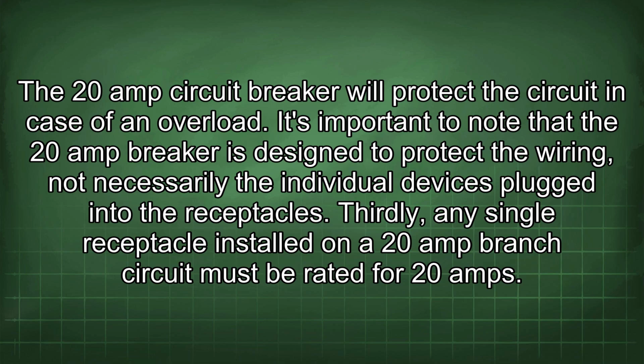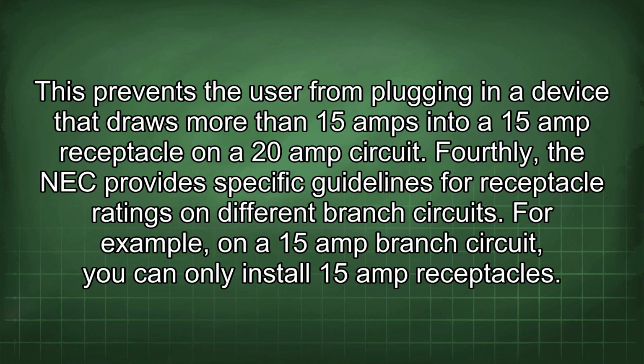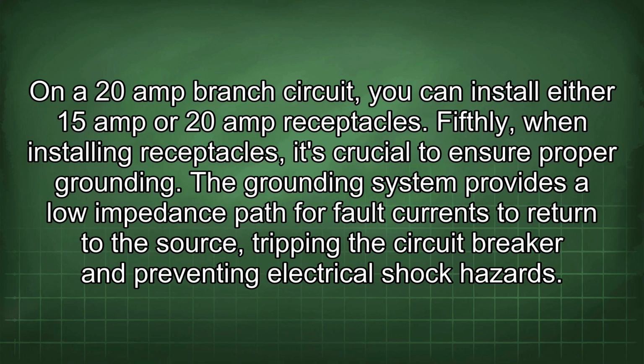plugged into the receptacles. Thirdly, any single receptacle installed on a 20 amp branch circuit must be rated for 20 amps. This prevents the user from plugging in a device that draws more than 15 amps into a 15 amp receptacle on a 20 amp circuit. Fourthly, the NEC provides specific guidelines for receptacle ratings on different branch circuits. For example, on a 15 amp branch circuit, you can only install 15 amp receptacles. On a 20 amp branch circuit, you can install either 15 amp or 20 amp receptacles.